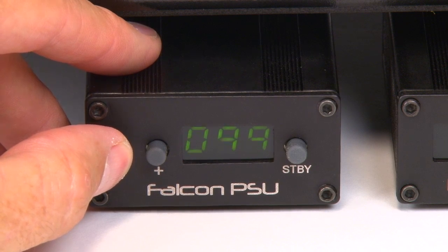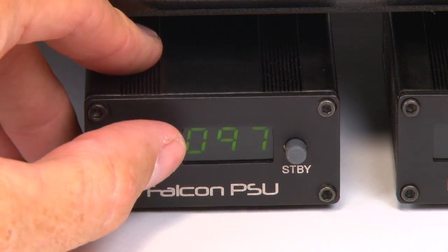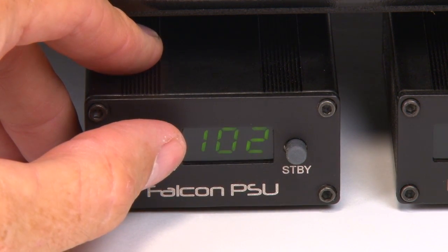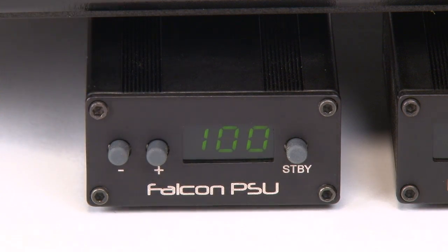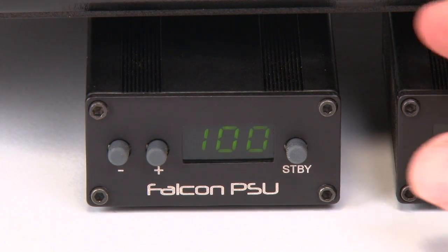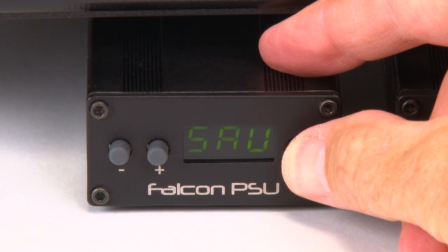Adjust the voltage for the new selection as before. When both speeds are properly adjusted, save the voltage output data by pressing and holding the standby button. The display will show SAV to indicate the data is stored, then revert to standby mode. Pulley selection mode.